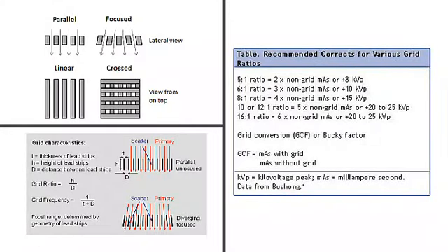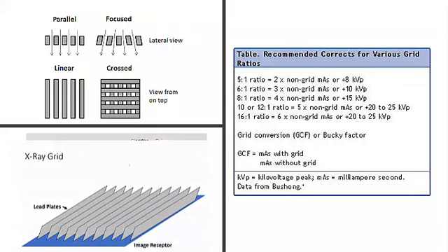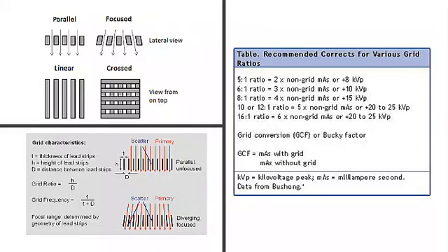Quick update on grids. There are many types of grids that are used in the X-ray department. There are parallel grids, there are focus grids, there are linear grids, and there are crosshatch grids. Use the correct grid and grid ratio for the subject that you're trying to capture. Not just the blue grid or the yellow grid, but when you look at the back of each grid, they are firmly labeled like 8:1 focus grid or 5:1 parallel grid. Focus grids must be used in a certain SID range, and no more and no less. If used at the wrong distance, you will totally defeat the purpose of using a grid and have grid cutoff.